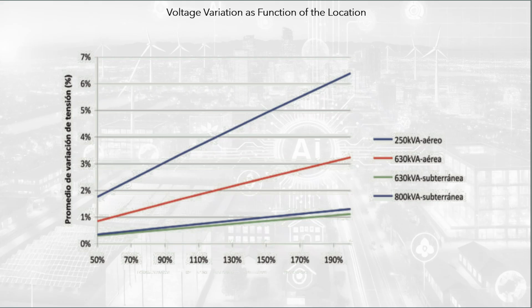There is a greater variation in tensions in aerial networks than in underground networks. Specifically, the 250 kVA aerial grid has the highest sensitivity to active power injection, as the grid is much longer than the rest. As it has higher impedances, the effect of the variation in power flows is also greater than in the rest of the networks.